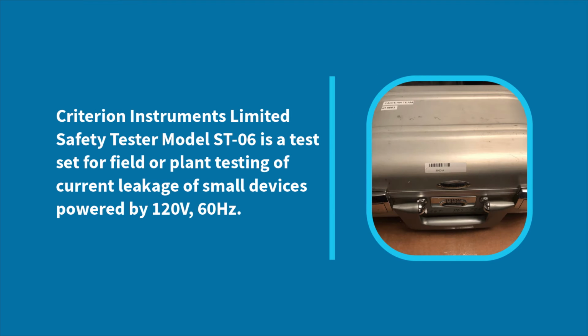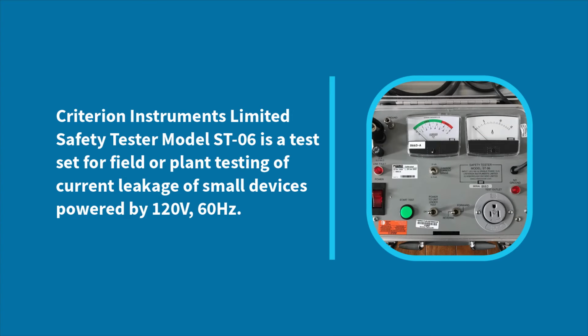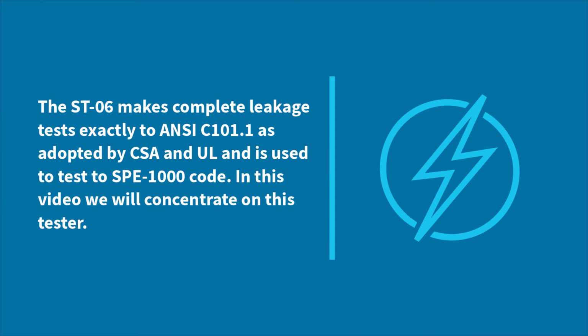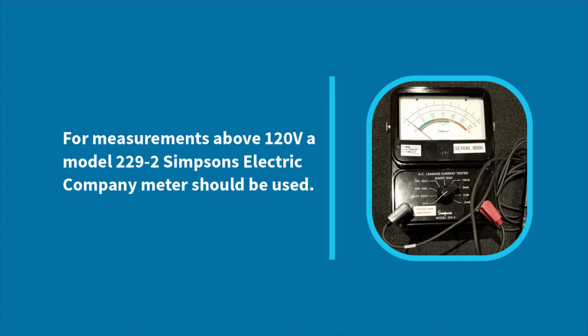Criterion Instruments Limited Safety Tester Model ST06 is a test set for field or plant testing of current leakage of small devices powered by 120 volts, 60 Hz. The ST06 makes complete leakage tests exactly to ANSI C101.1 as adopted by CSA and UL, and is used to test a SPE 1000 code. In this video, we will concentrate on this tester. For measurements above 120 volts, a Model 229-2 Simpson's Electric Company meter should be used.